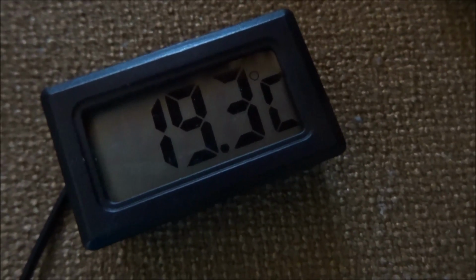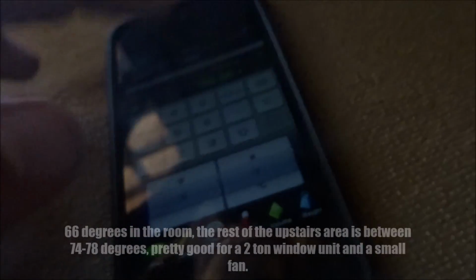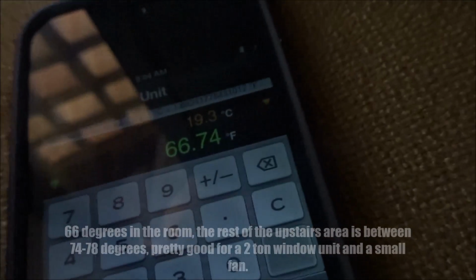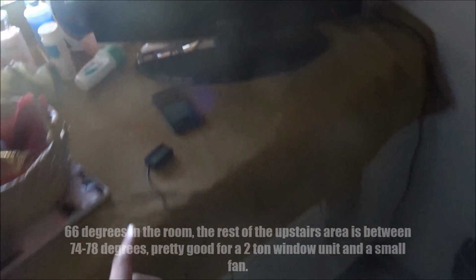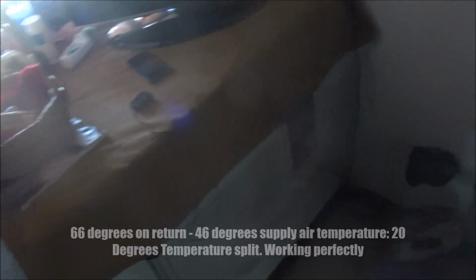Okay, we got the thermometer sensor right where the thermostat is, right down here in the inside part. Right, not touching the coil, but it's right on this side of the return. We got a return temperature of 19.3 degrees Celsius. That's 66 degrees Fahrenheit, and the supply temperature was 8.1 degrees Celsius, which was 45, I believe, 46 Fahrenheit.